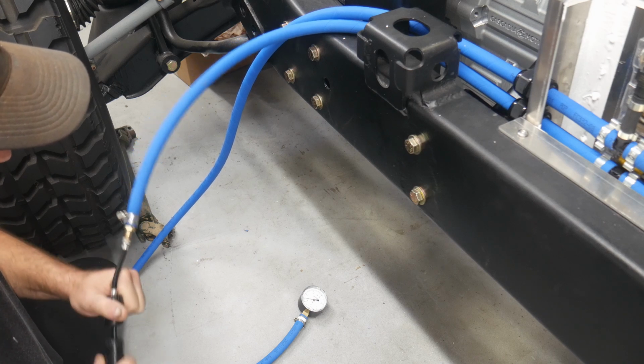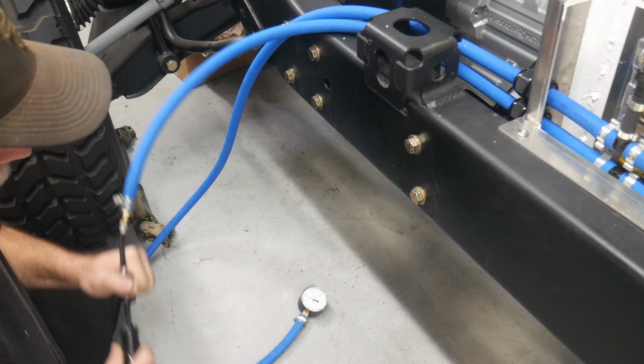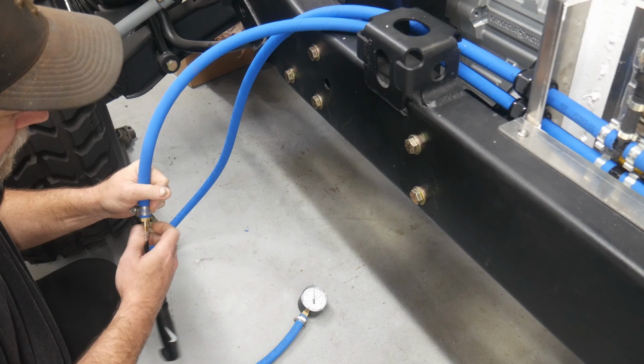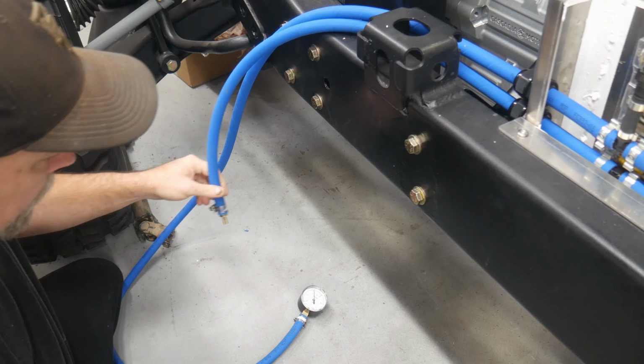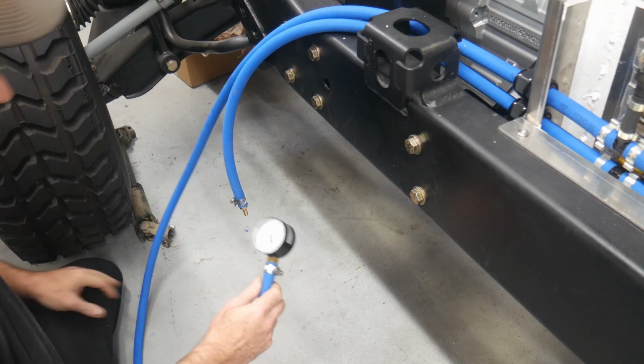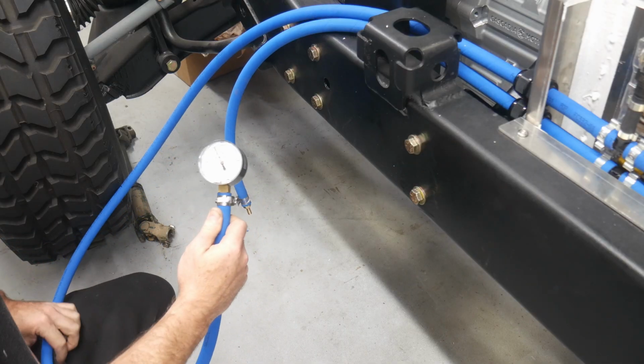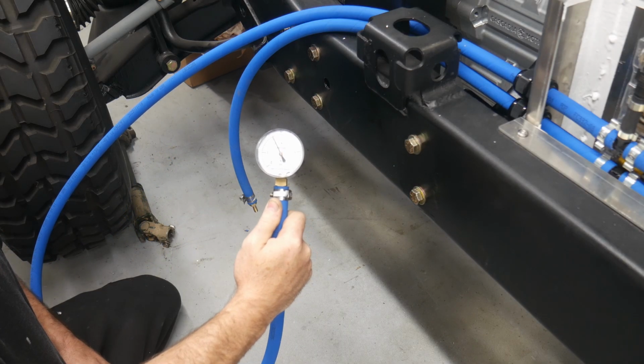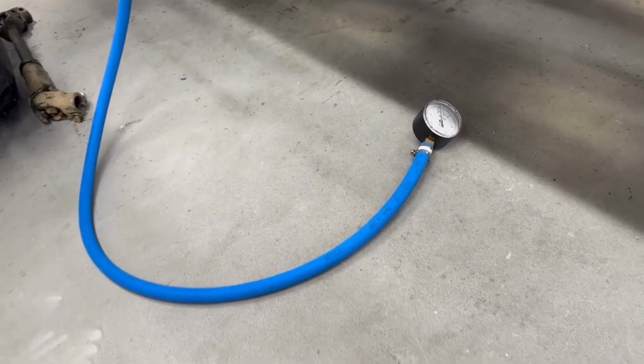Finally, I am testing the cooling lines to ensure that we have no leaks. I am testing this at just over 2 psi using a Schrader valve with a bicycle pump to pump in air at one of the lines and a gauge at the other line. I left this gauge on overnight and it held.